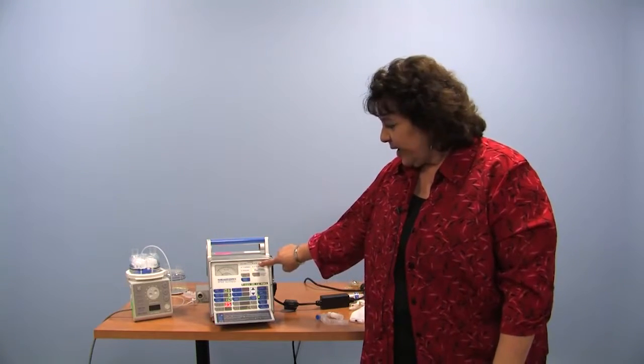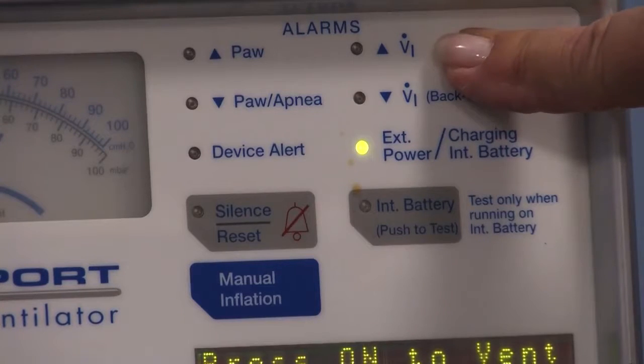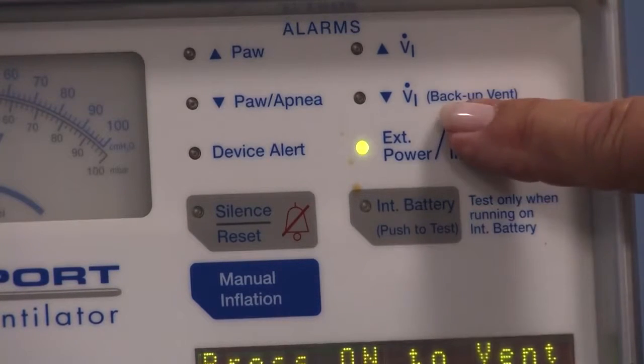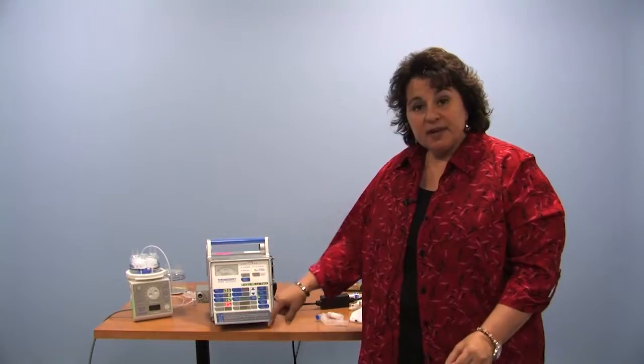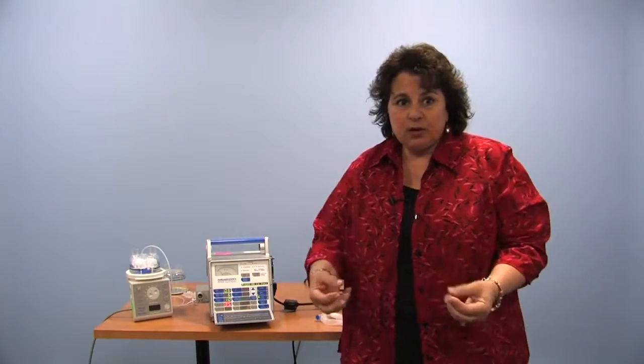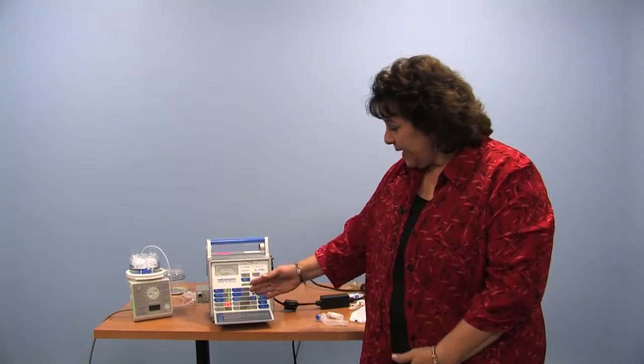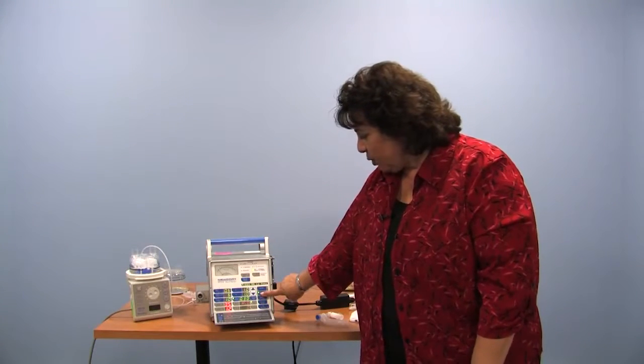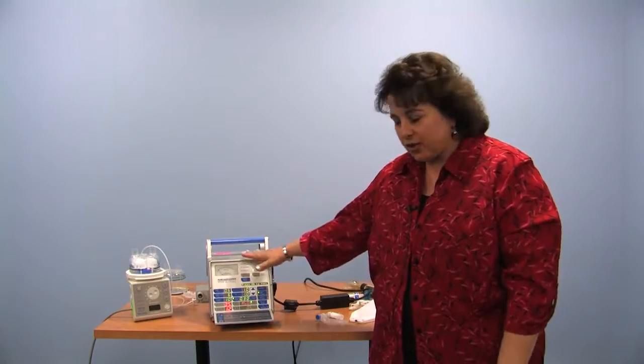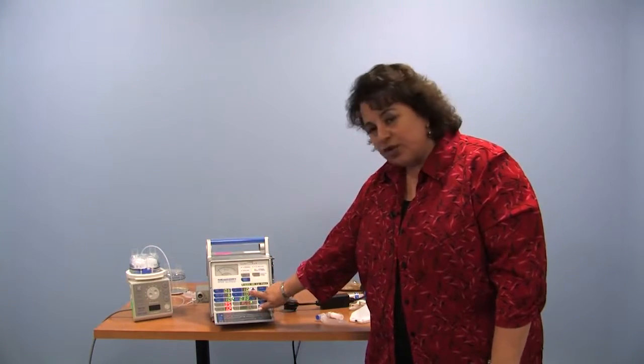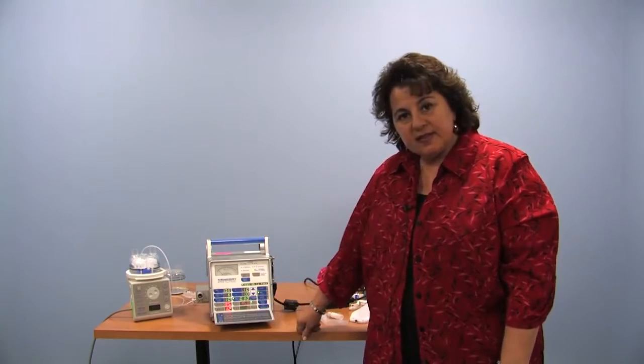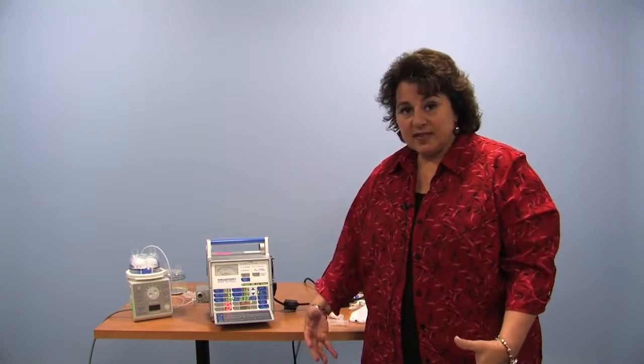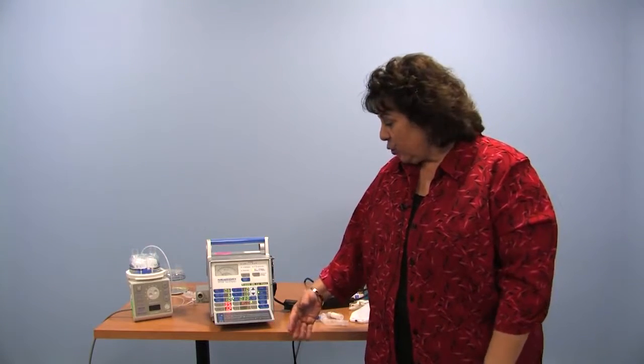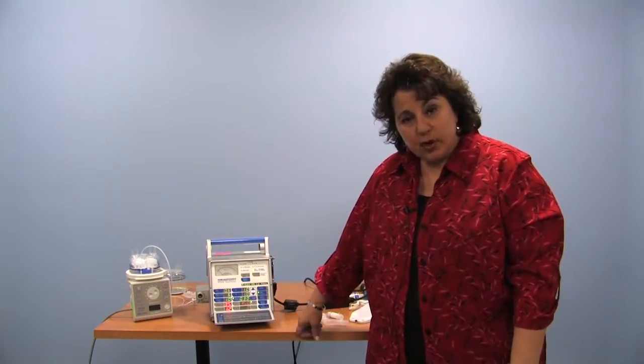Over here we have high VI, which stands for high minute ventilation alarm, and low minute ventilation alarm. Minute ventilation is a mathematical term for how many breaths a minute multiplied by the size of the breath. So right now, if we went back to the SIMV mode where we were before, if our patient was sound asleep and the machine gave 10 breaths and they were 300 cc's each, that would be 3,000 cc's in a minute. The machine's going to read that for us in the parameter window, which I'll show you in a few minutes.